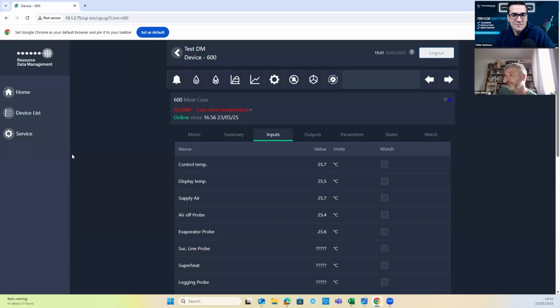If it's the suction, am I doing something wrong with my case setup? Have I got the superheat setting too small and we're into unstable? Have I got the response time too fast and the valve's hunting? Have I got a poor airflow over the coil and a little tiny change in the valve is killing the suction temperature? If it's the evaporating temperature that's moving, then is it the rack's not stable? Is my transducer all right? What's causing that reading to move up and down?